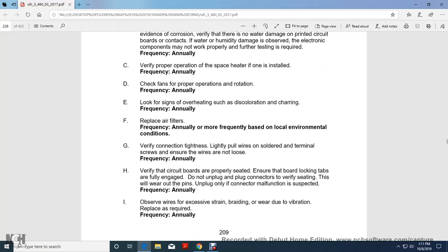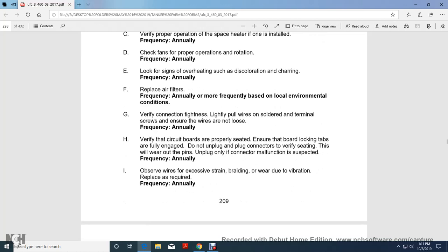Replace air filters annually, or more frequently based on local environmental conditions. Verify connection tightness. Lightly pull on wires at solder joints and terminal screws to ensure the wires are not loose, annually. Verify circuit boards are properly seated, with the edge of the board and locking tabs fully engaged.